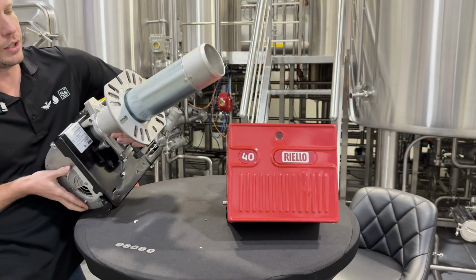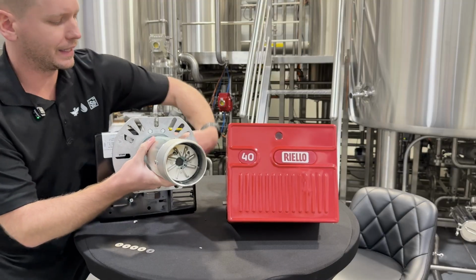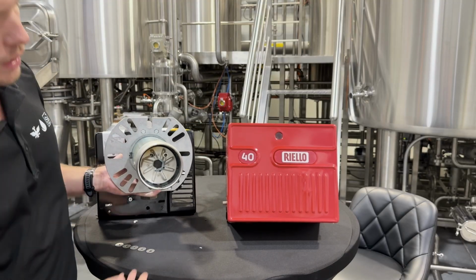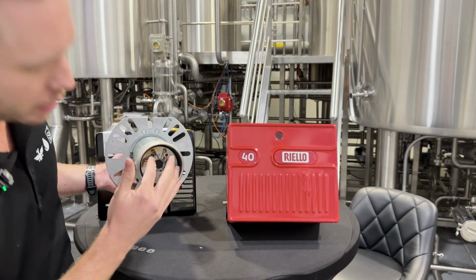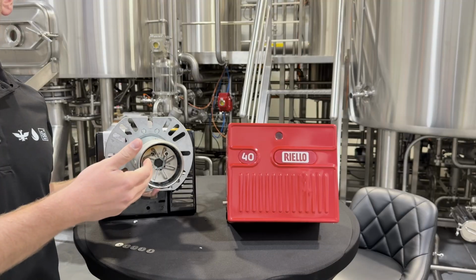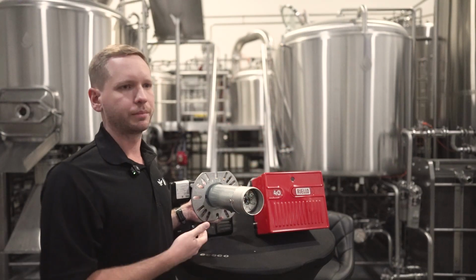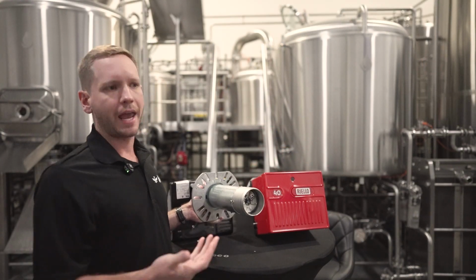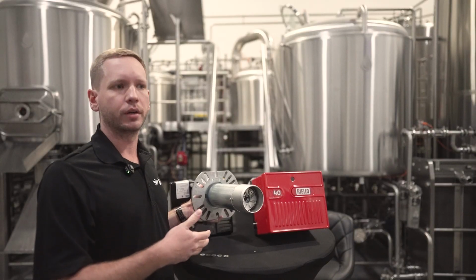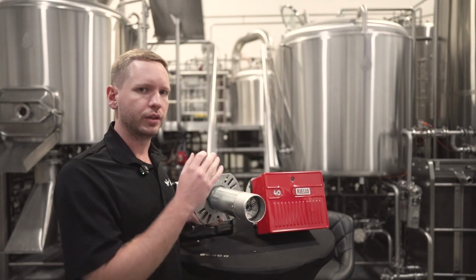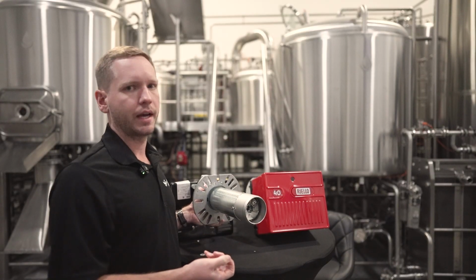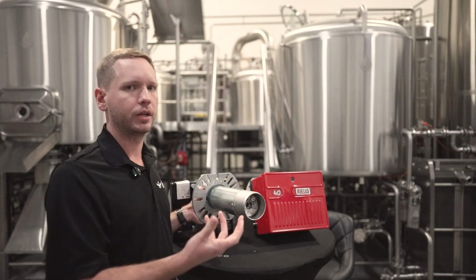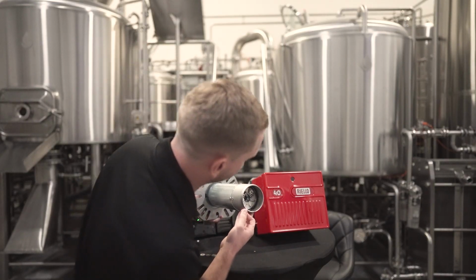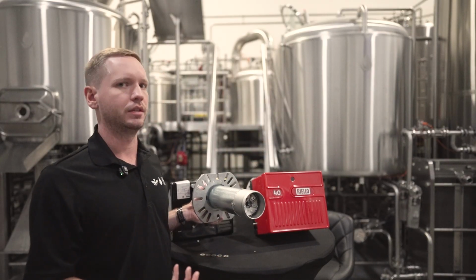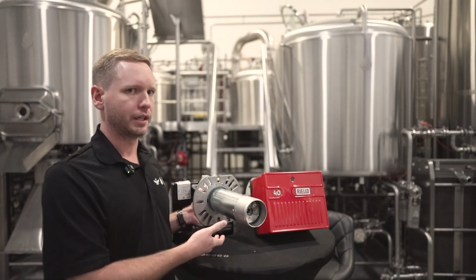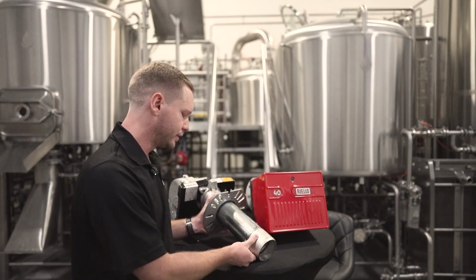If for whatever reason that's still not working and you really need to get into the burner itself, you can always make sure that these probes are cleaned and maintained. Not something you need to do often, but an annual quick look at your burner would be recommended, just to make sure that those are clean, that you're getting good contact from any spark happening on that ignition probe, and that the ionization probe can actually sense any change in the air chemistry within the burner itself.